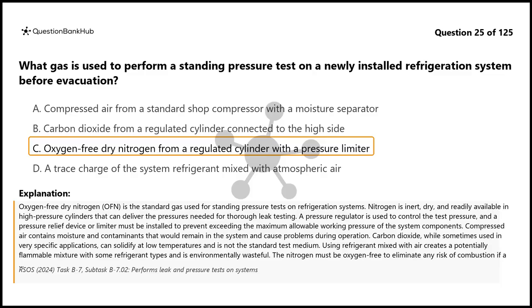Compressed air contains moisture and contaminants that would remain in the system and cause problems during operation. Carbon dioxide, while sometimes used in very specific applications, can solidify at low temperatures and is not the standard test medium. Using refrigerant mixed with air creates a potentially flammable mixture with some refrigerant types and is environmentally wasteful. The nitrogen must be oxygen-free to eliminate any risk of combustion if a leak occurs near an ignition source during the test.